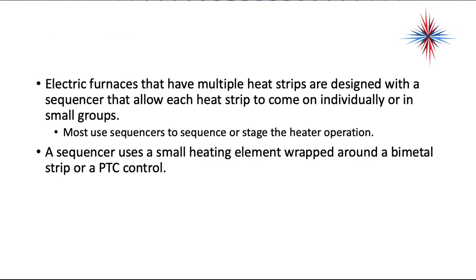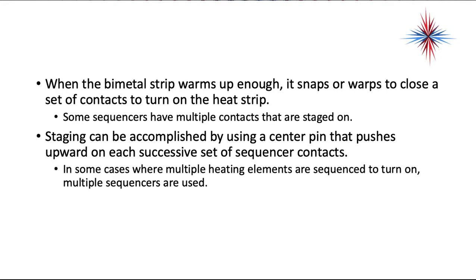Electric furnaces that have multiple heat strips are designed with a sequencer that allows each heat strip to come on individually or in small groups. Most use sequencers to sequence or stage the heater operation. A sequencer uses a small heating element wrapped around a bimetal strip or PTC, that's a positive temperature coefficient control. When the bimetal strip warms up enough, it snaps or warps to close a set of contacts to turn on the heat strip. Some sequencers have multiple contacts that are staged on. Staging can be accomplished by using a center pin that pushes upwards on each successive set of sequencer contacts.